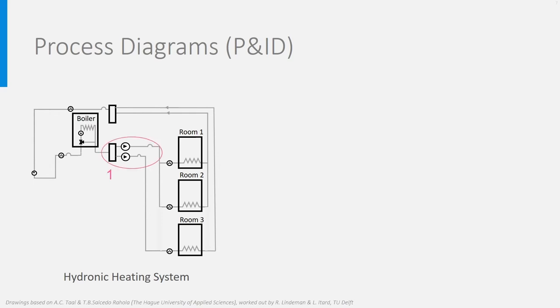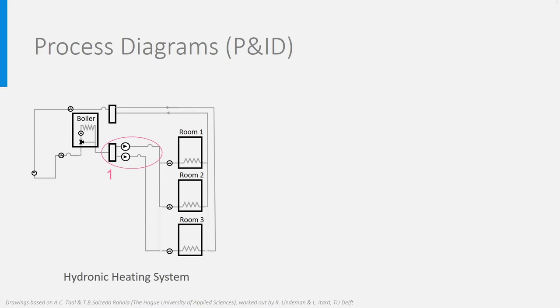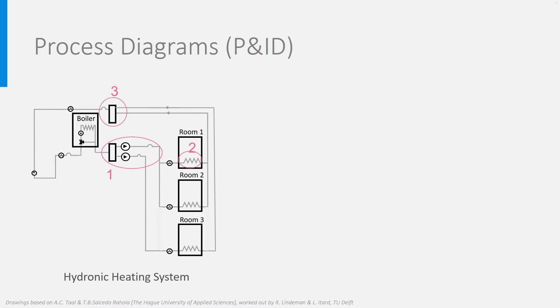You see here, at point 1, the divider where the hot water is divided to these two zones and pumped to the zones. The black triangle is a pump. You see valves further in the ducts to regulate the water flow. It can be switched on or off or in between. The radiators in the rooms are indicated by this resistance symbol in 2. Once the water has been cooled down in the radiators, it is collected for both zones here in 3 and further led to the boiler where it is heated again.